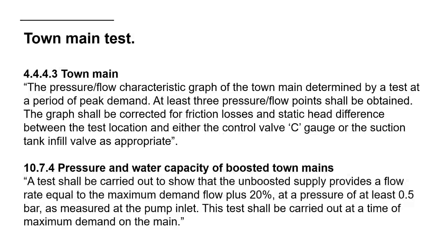Again, very much like you would do with a calculation for a fire pump. You then correct for frictional losses and static head, i.e. that's what we've got at the town main at this point, so is that going to be sufficient by the time we get to the end of our sprinkler system? Then we can make a decision as to whether or not that is appropriate. Again, very much like a fire pump. When we're sizing a fire pump, we want it to cover the certain pressure and flow points on our graph. Well, does the town main do that or not?